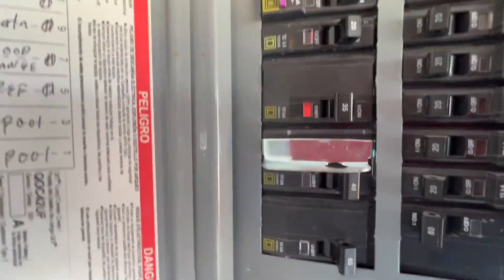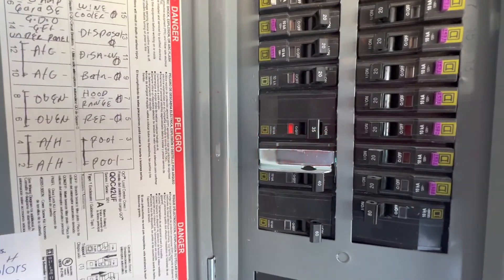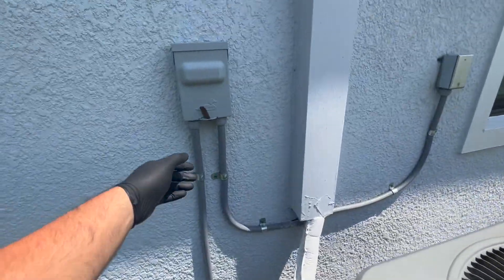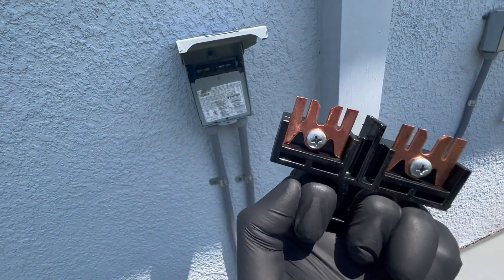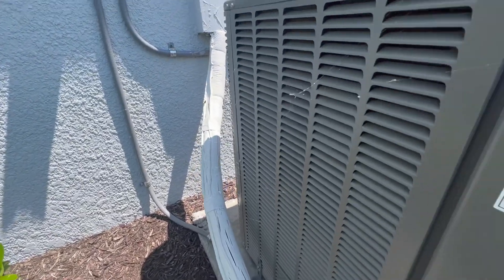We're here for a no-cool call. The breaker for the AC units 12 and 10 is tripped. Before we do anything else, we want to make sure everything's safe before we turn it on. We're gonna check the other unit — doesn't seem burnt, just some spider webs.